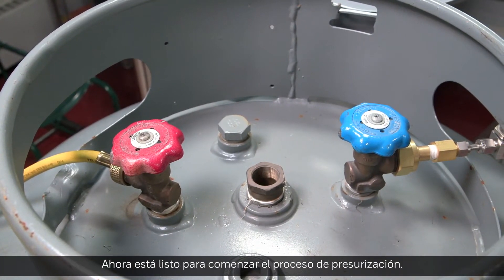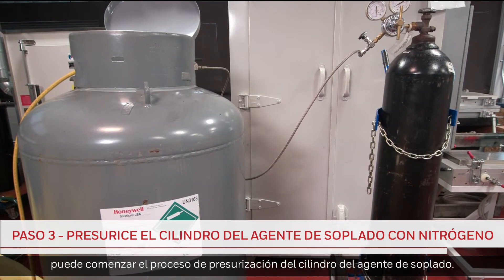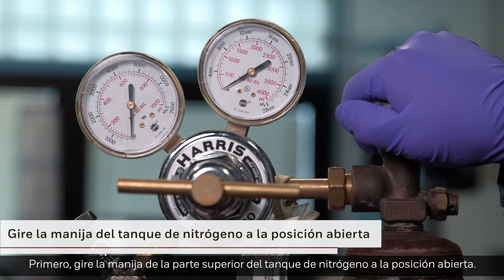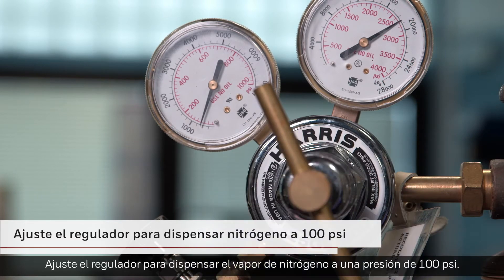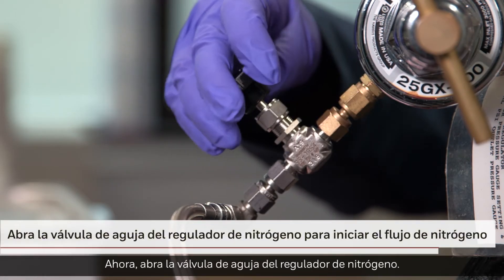You're now ready to begin the pressurization process. Now that the lines are connected, the process of pressurizing the blowing agent cylinder can begin. First, turn the handle on the top of the nitrogen tank to the open position. Adjust the regulator to dispense the nitrogen vapor at 100 PSI pressure. Now, open the needle valve at the nitrogen regulator.